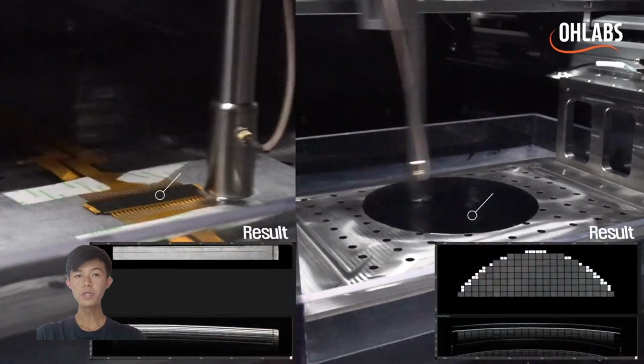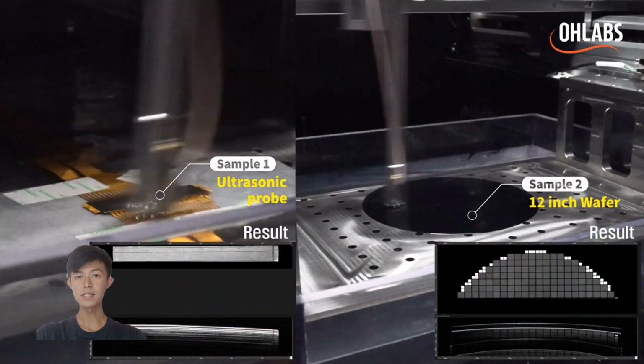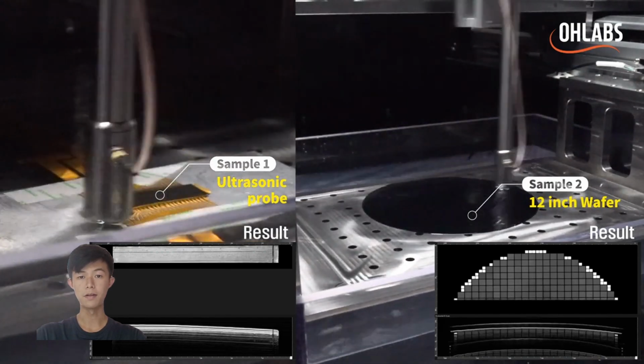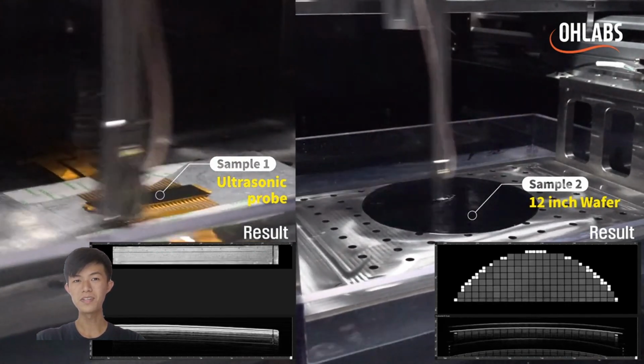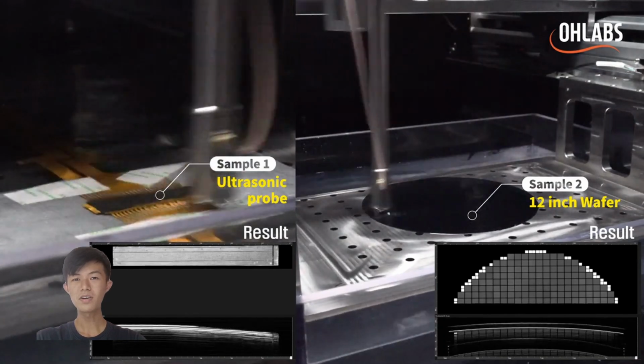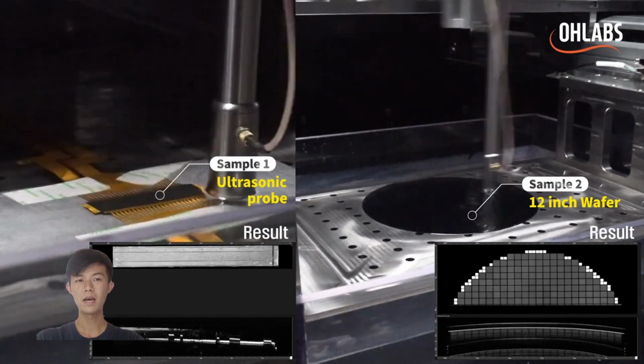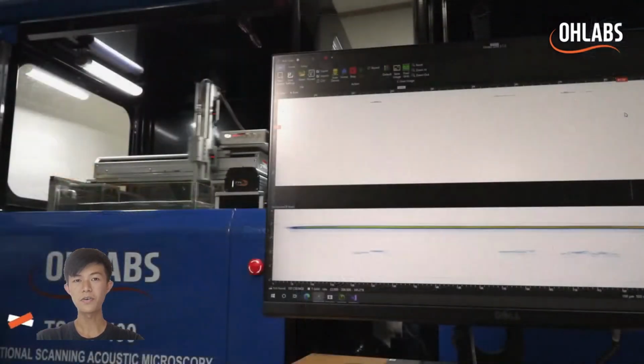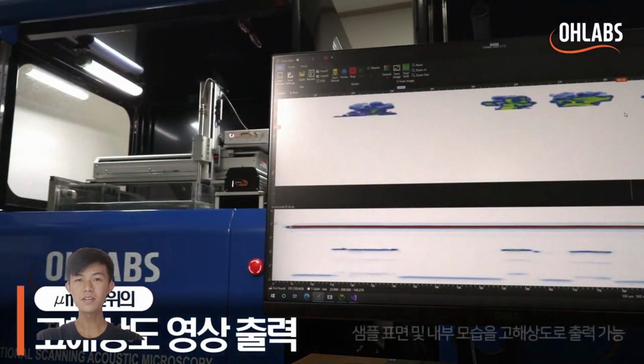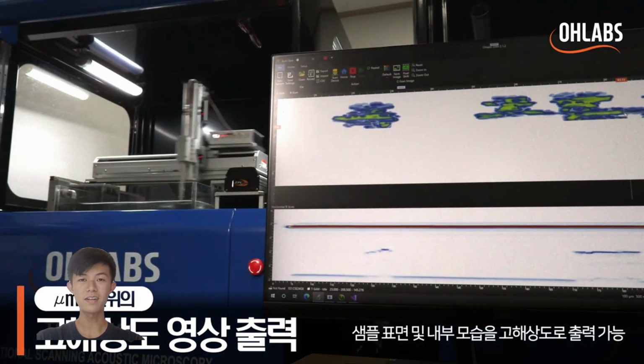To form a 2D image, the transducer scans the sample in a systematic pattern. Each scan position produces one data point based on the reflected signal. By repeating this process across the surface, a full internal image is reconstructed for analysis.